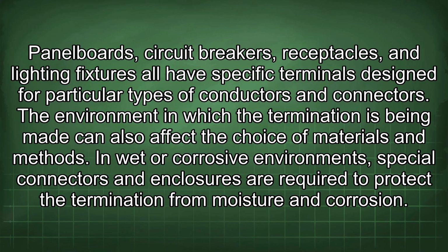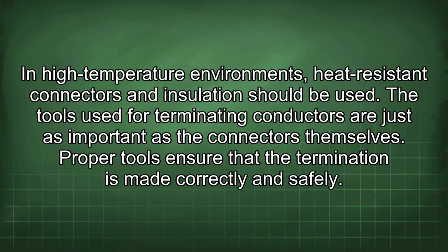The environment in which the termination is being made can also affect the choice of materials and methods. In wet or corrosive environments, special connectors and enclosures are required to protect the termination from moisture and corrosion. In high-temperature environments, heat-resistant connectors and insulation should be used. The tools used for terminating conductors are just as important as the connectors themselves. Proper tools ensure that the termination is made correctly and safely.